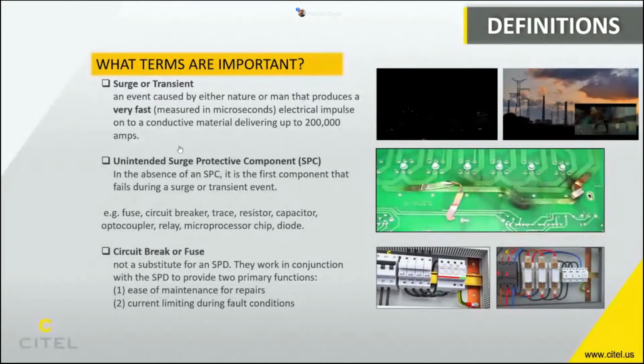It didn't. In surge protection we do use circuit breakers and fuses, but not because they assist in the surge protection function. We use them to make maintenance easier, disconnecting the SPD to replace a module, and to help limit current during a fault. The reason they don't offer assistance is because they're too slow.